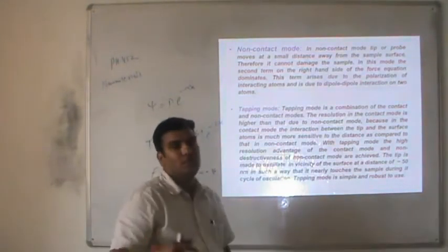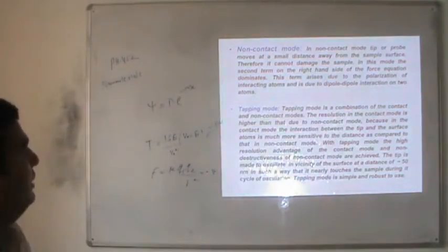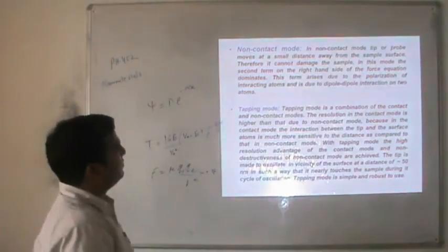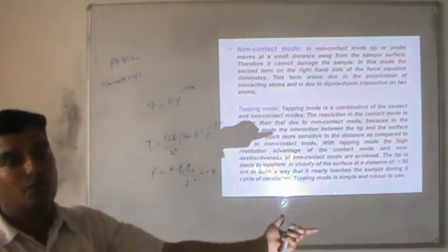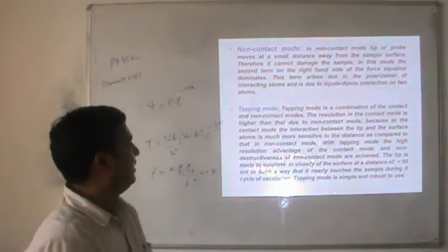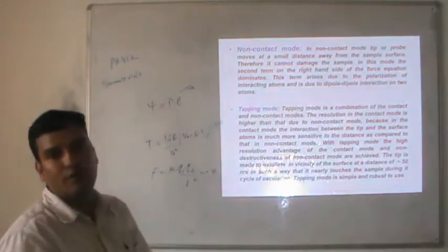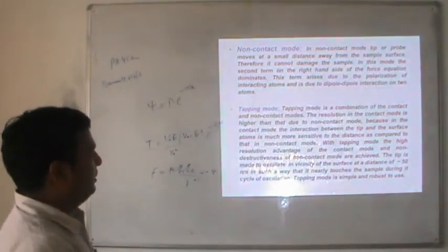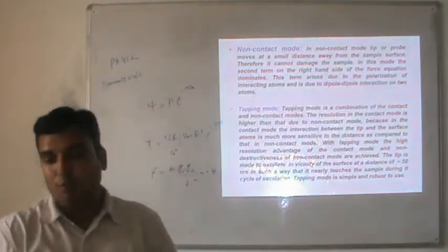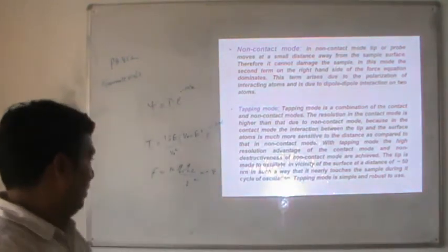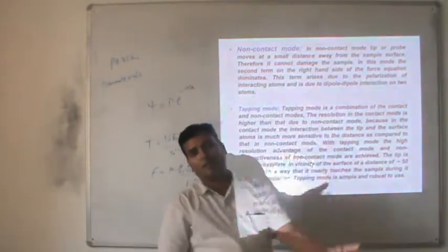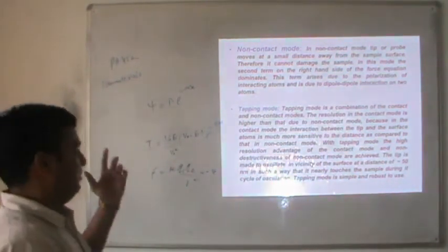In non-contact mode, the tip moves at a small distance away from the sample surface and cannot damage the sample. The attractive force term dominates, arising due to the polarization of interacting atoms and dipole-dipole interaction. Tapping mode is a combination of contact and non-contact modes. The resolution in contact mode is higher because the interaction between tip and surface atoms is more sensitive to distance. With tapping mode, the high resolution advantage of contact mode and the non-destructiveness of non-contact mode are both achieved.